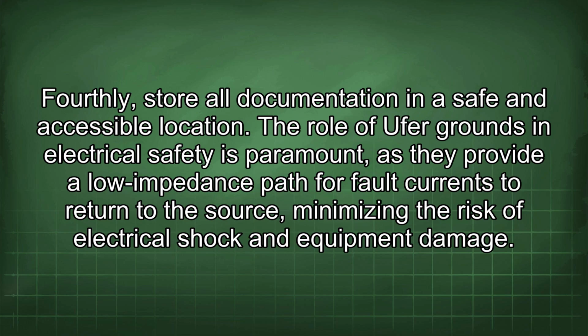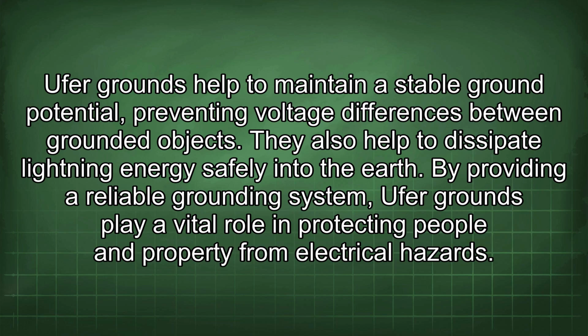The role of Ufer grounds in electrical safety is paramount, as they provide a low impedance path for fault currents to return to the source, minimizing the risk of electrical shock and equipment damage. Ufer grounds help to maintain a stable ground potential, preventing voltage differences between grounded objects. They also help to dissipate lightning energy safely into the earth. By providing a reliable grounding system, Ufer grounds play a vital role in protecting people and property from electrical hazards.